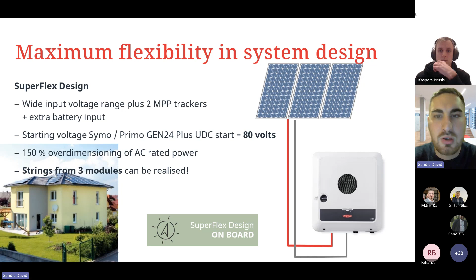It is also possible to over-dimension the hybrid inverter up to 50%. So, for example, on a 10 kilowatt device, you can really put 15 kilowatts on the DC side into the inverter. This normally makes sense, for example, on an east-west oriented PV system. So from 3 modules up, you can connect on the DC side. And of course, you have the 2 MPP trackers, and the battery input is also in our device.